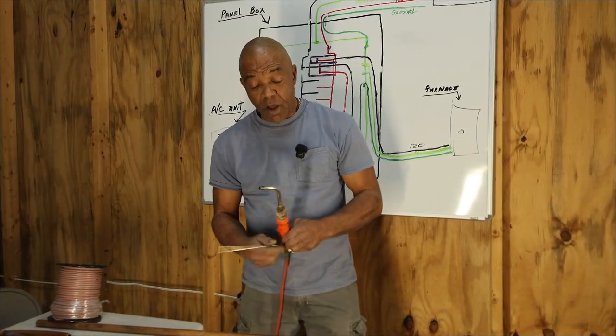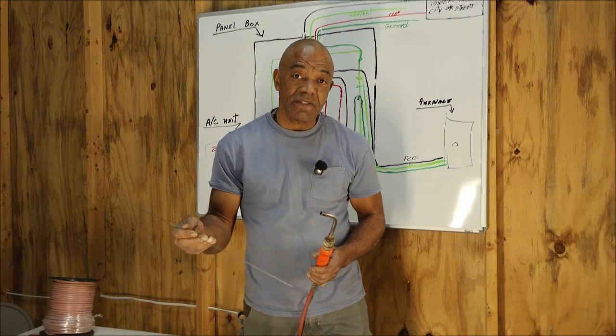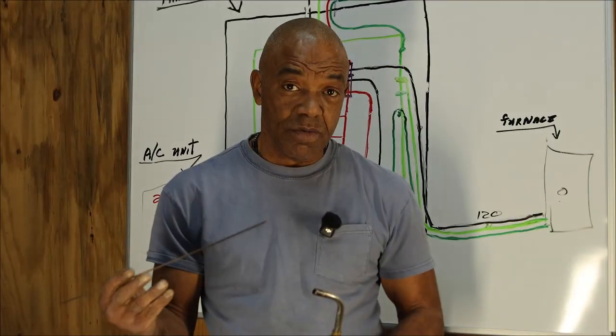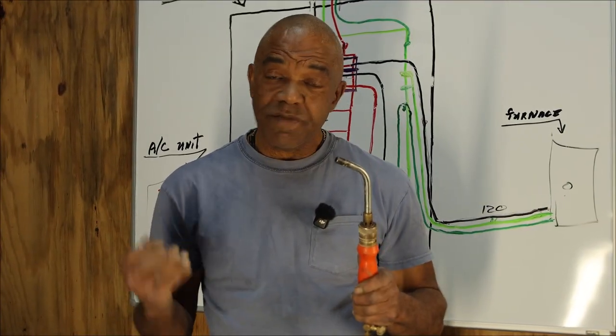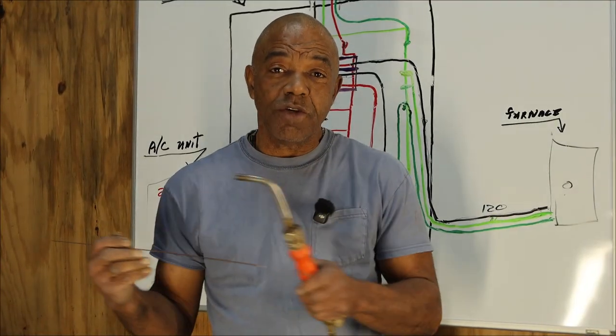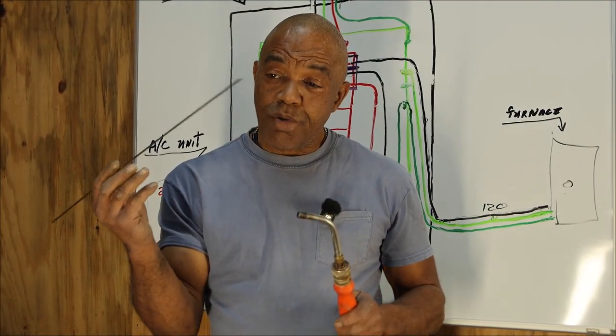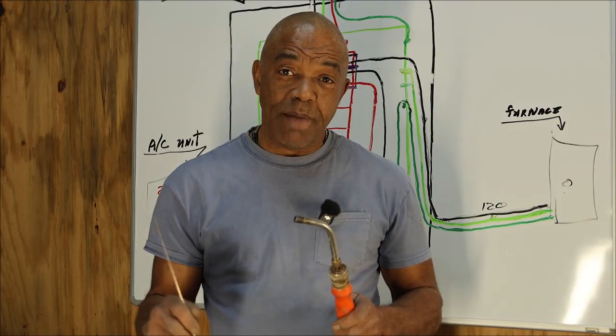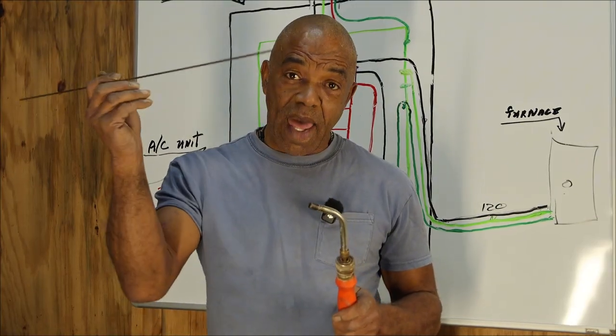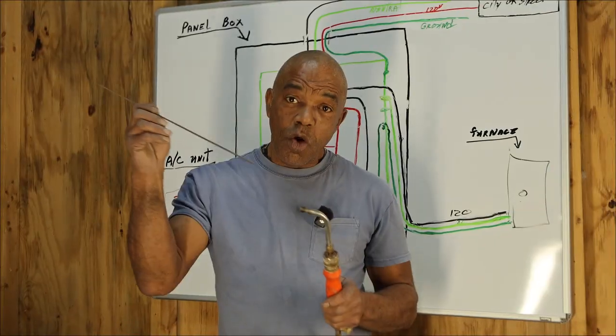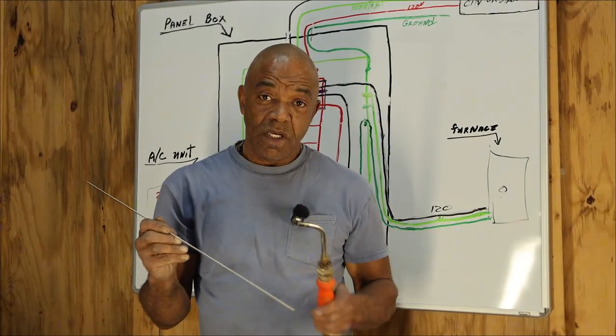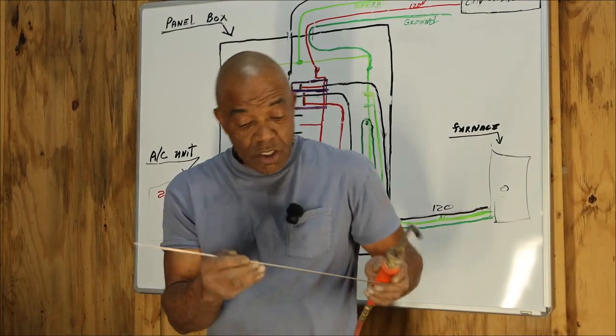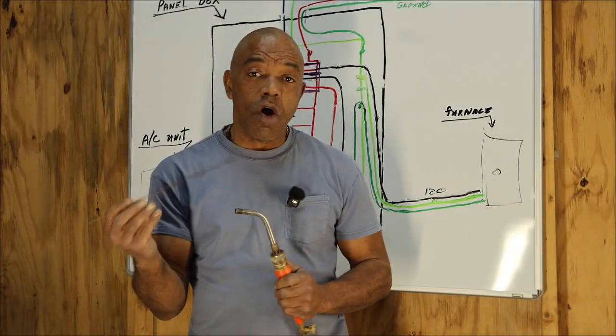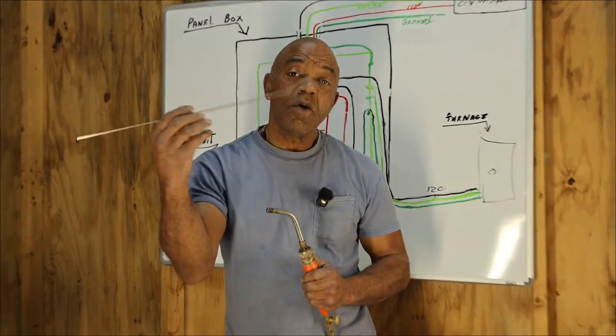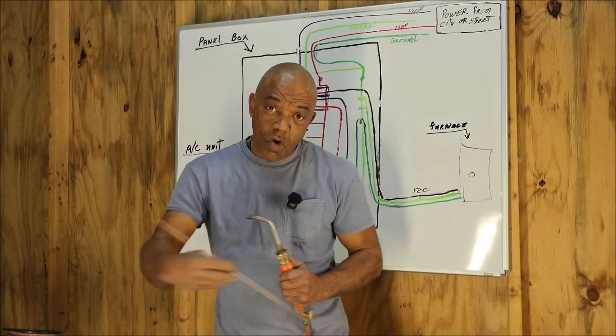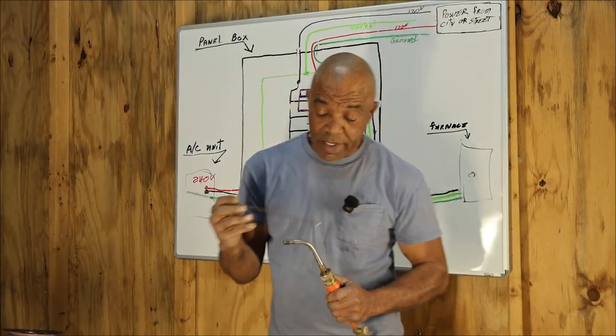Now, there is a method to brazing. Heat is very important, the use of your heat. As you get the pipe hot, the alloy in the brazing rod will follow the heat. So you've got to use the heat to draw the solder, or the brazing rod, where you want it, which is into the connection.